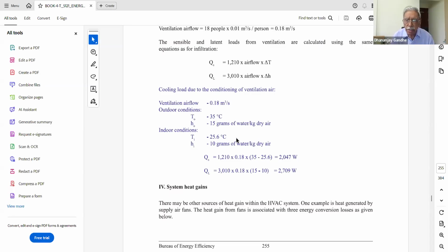So that is called the ventilation load. That amount of air has to be supplied. There are some air changes specified in the air conditioning system, so you will have to supply that much air at intervals. That constitutes the ventilation system gain.